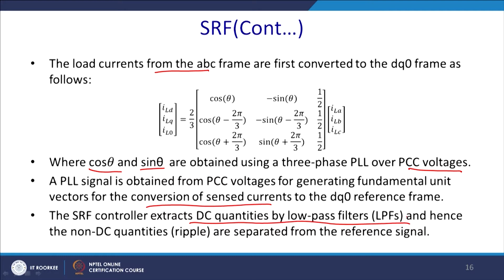The SRF control extracts the DC quantities by a low pass filter, and hence the non-DC quantities, that is the ripple, are separated from the reference signal, and if it is contaminated with noise, that also gets eliminated. So, ultimately you have a D axis and Q axis component of current consisting of the DC. The fundamental component will look like a DC in the DQ frame, and the ripple, negative sequence as well as harmonics, will appear as second order, because it is rotating at a speed of omega.